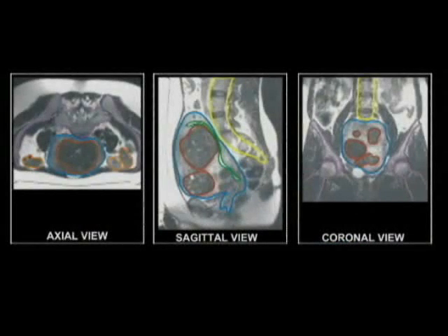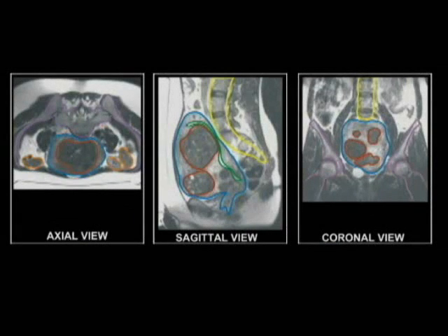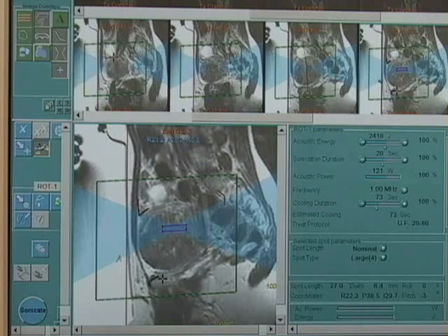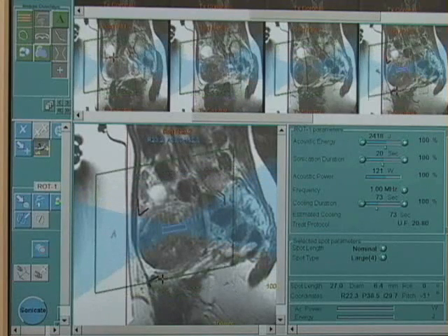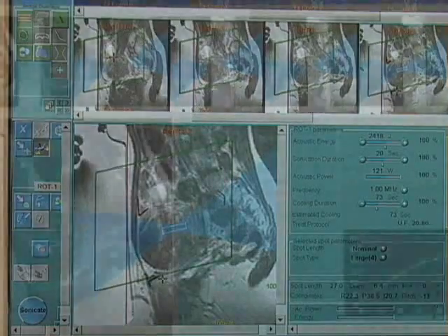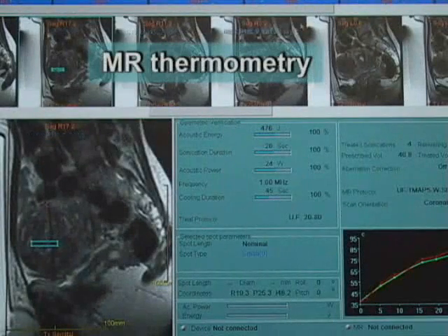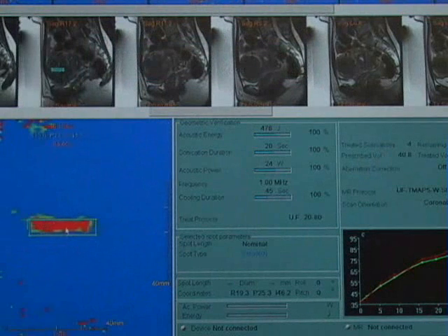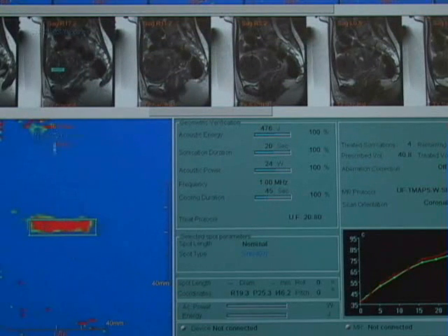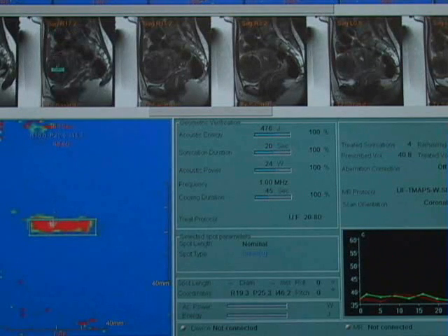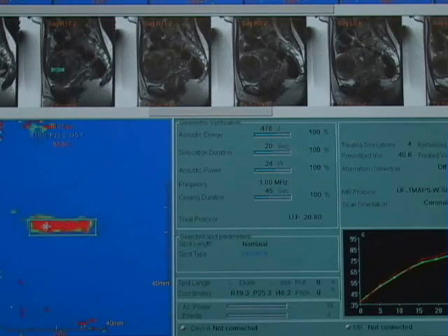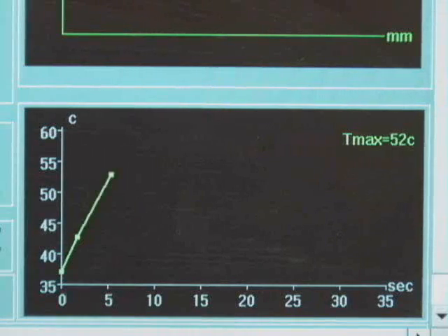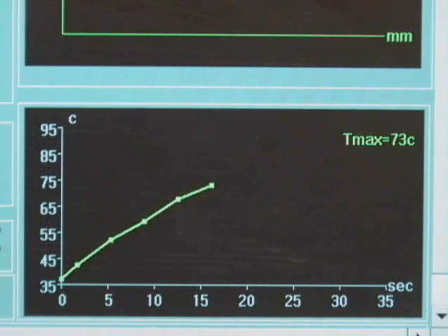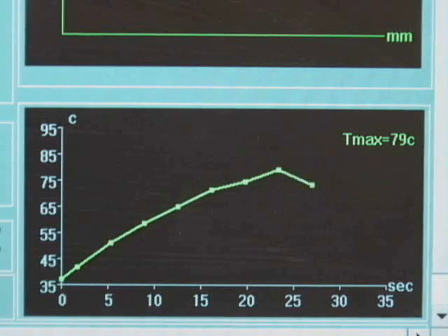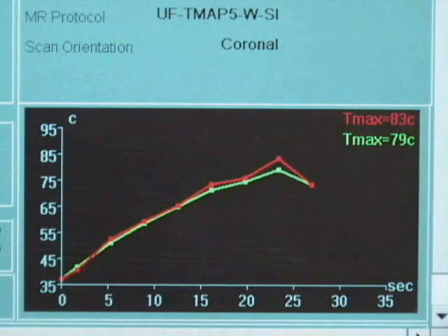This visualization enables the physician to clearly identify the anatomy and treatment target, as well as the energy beam path, to verify that the energy does not damage healthy tissue, ensuring safe treatment. A unique feature of magnetic resonance is the ability to measure thermal changes in the tissue, a measurement to predict tissue ablation. Every 3 seconds during the energy delivery, thermal MR images display the temperature buildup in the targeted spot and surrounding tissues, ensuring that the energy in the target is high enough for coagulation and not in the surrounding tissues. The evolving temperature graph shows the hottest temperature in the sonication.